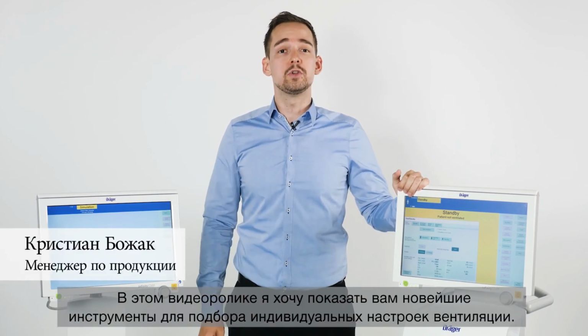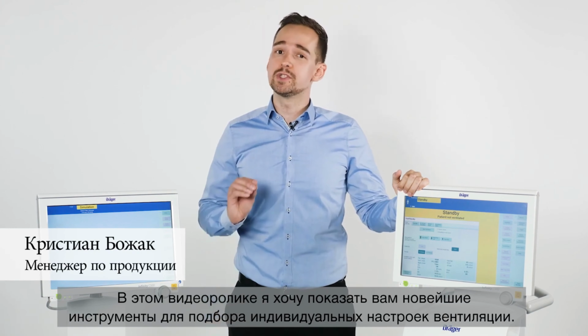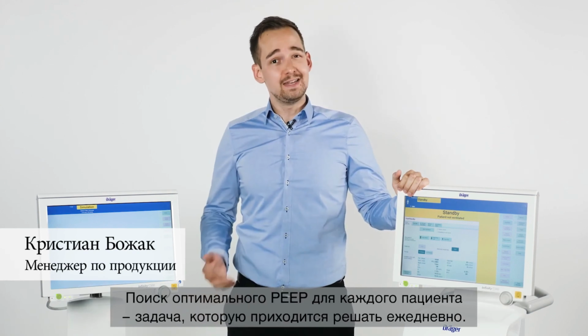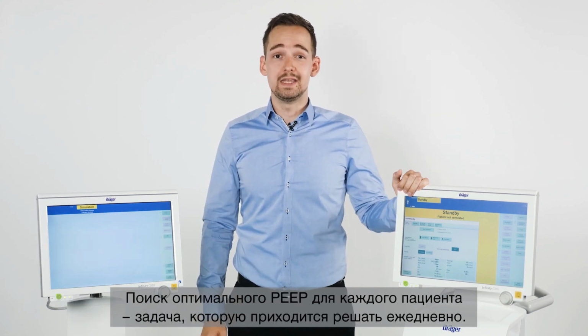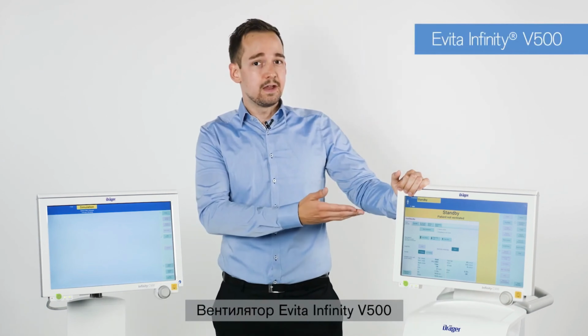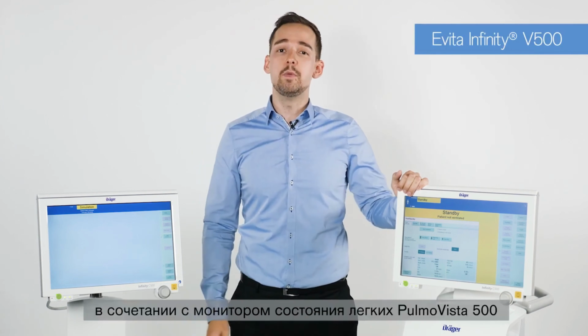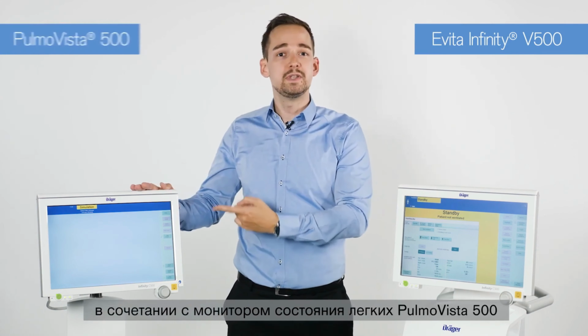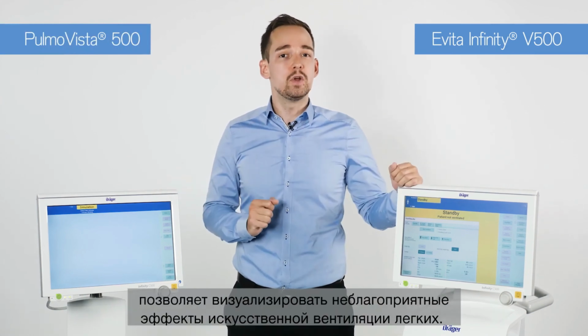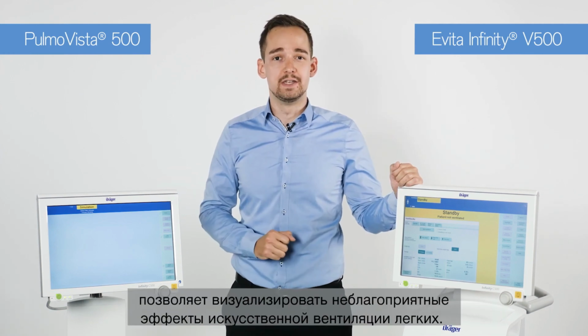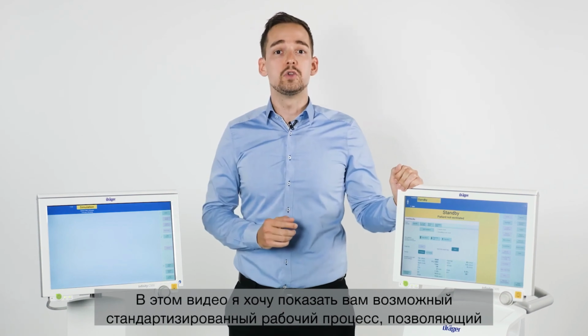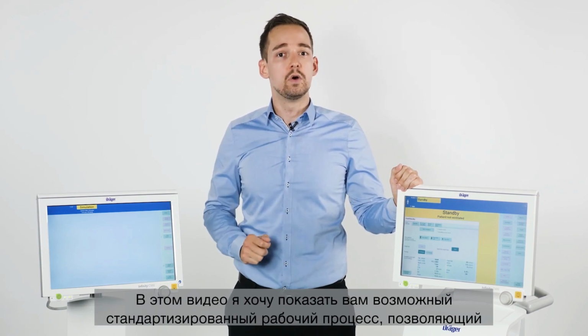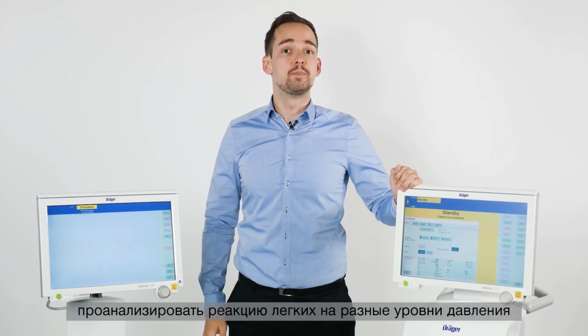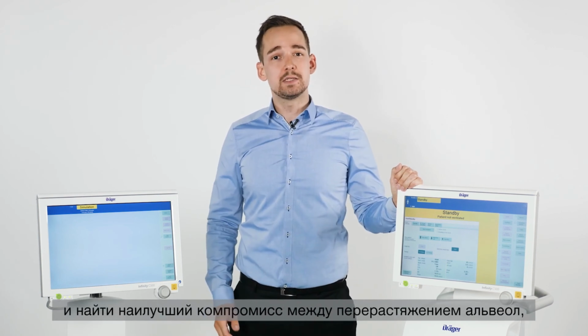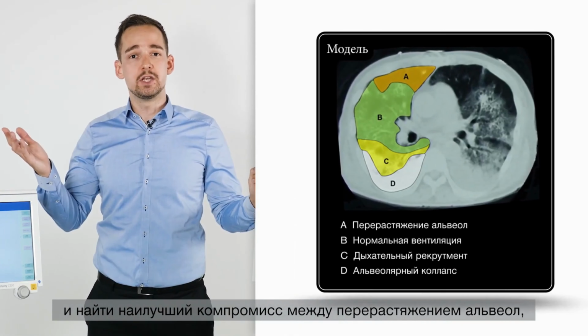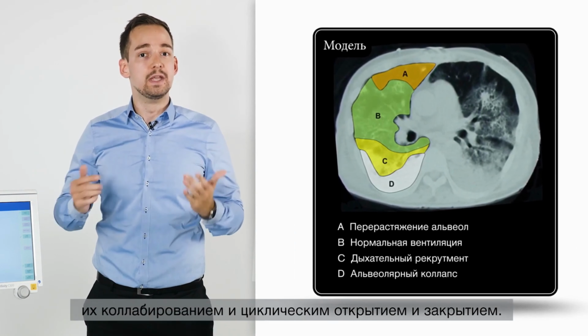Within this tutorial, I want to show you the latest tools for personalized ventilation. Finding the best PEEP for each individual patient is a daily challenge. The Evita Infinity V500 ventilator, in combination with the lung function monitor PulmoVista 500, allows to visualize the adverse effects of mechanical ventilation. In the following video, I want to show you a possible standardized workflow to analyze the lung's response to different pressure levels and to find the best compromise between alveolar overdistension, collapse, and cyclic opening and closing.